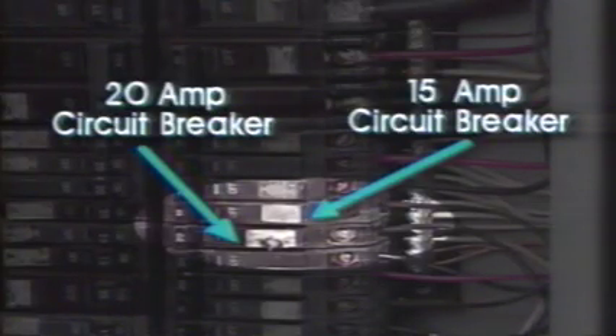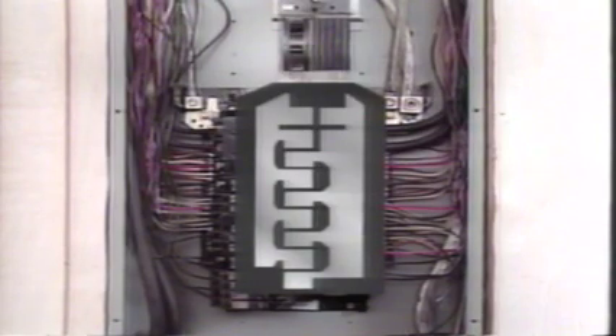Single pole breakers are usually rated for 15 or 20 amps. The double pole 240 volt circuit breaker has two hot lines. This circuit breaker is connected to and draws current from both bus bars. The bus bars have a zipper tooth configuration, and the metal clips of the circuit breakers make the connection with the bus bar. Double pole circuit breakers are usually rated for 30 amps and supply power to high amperage appliances such as electric ranges, air conditioners, electric dryers, and so on.